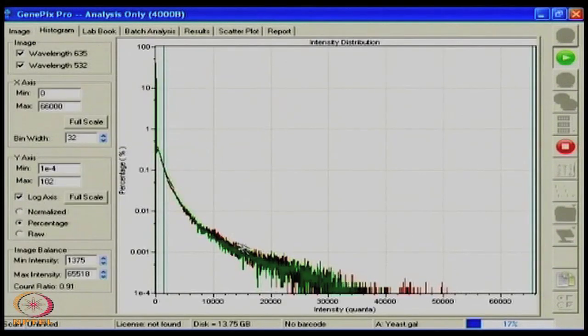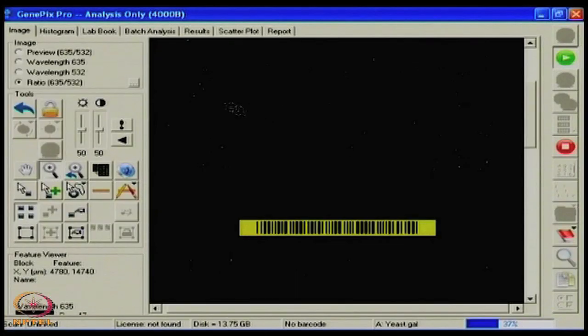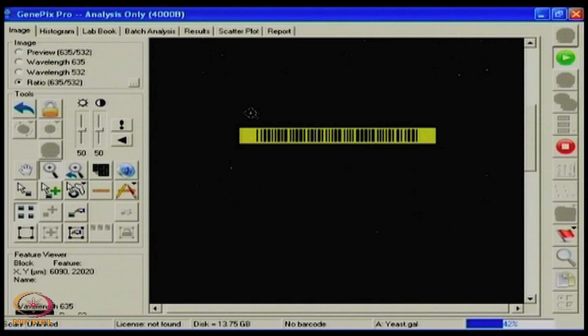Let us quickly go through one particular scan which is a simultaneous scan, meaning both lasers will be acquired at the same time. If I press the data scan button, after putting the inverted slides in the hardware it starts scanning. If I use the zoom button you can see how the scanning is happening. You can look at different image types. If I click on only one wavelength, you can see it going for the ratio image scan. Now quickly switching to the histogram you can see it starting to come up because scanning is going on live, and it starts to develop - basically as discussed, the channels should be overlapping, and my settings are looking very nice in this particular one.